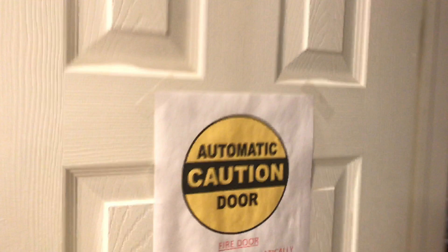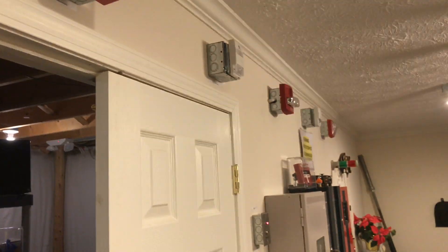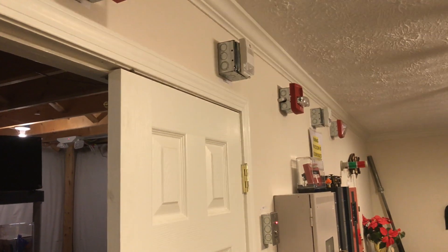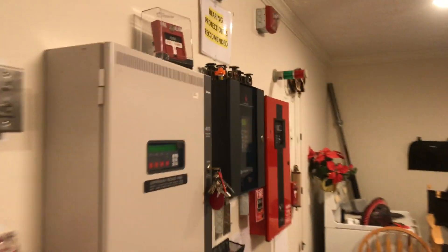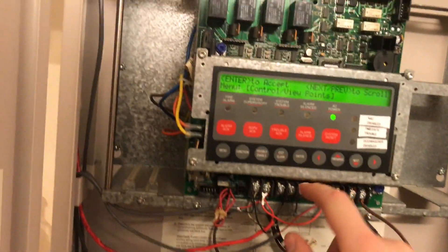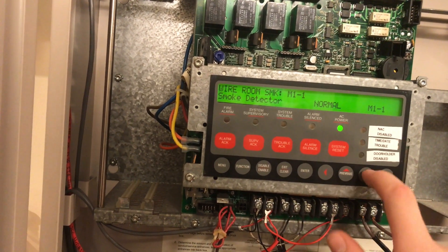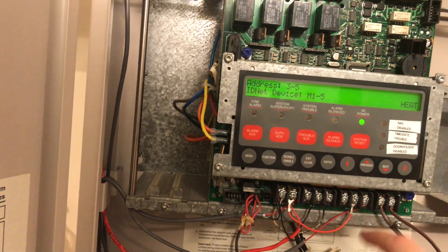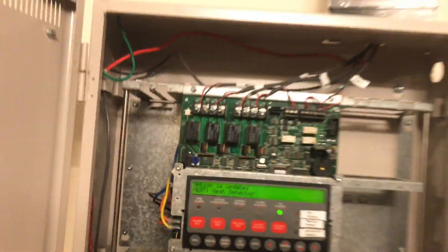The panel is resetting, then after that we'll reset the door and heat test the heat detector. We'll get the door ready to reset — strobes continue to flash. Let me grab my lighter. We'll bring up the heat detector and watch it as it goes.